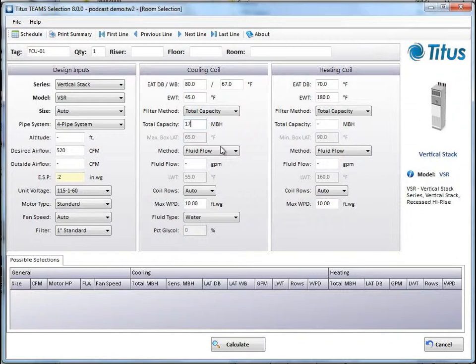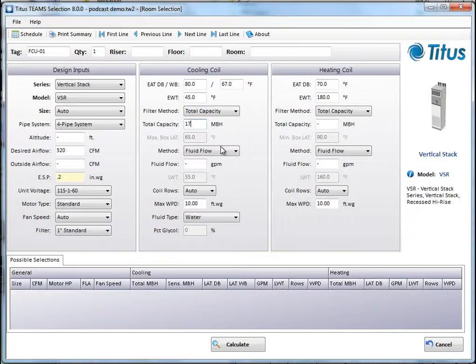Okay, so before I go on, I want to mention that sometimes putting in the air flow and the capacity is too strict of a calculation, and the program won't come up with a selection. If that's the case, then you should put in just air flow and not capacity, or just capacity and not air flow, and let the program do the math that works out. So it'll show you all the fan coils that will meet your needs, and you can pick the one closest to your actual application requirements.